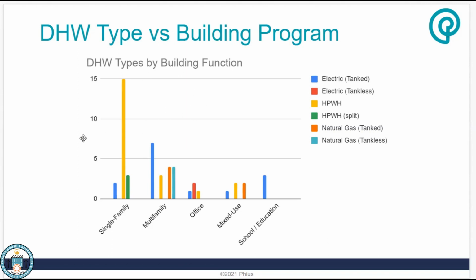So going back to this breakdown though, for single families, the vast majority are using heat pump water heaters, only a handful are using electric tanked water heaters. Multifamily is kind of the opposite: a lot of them are using electric tanks or natural gas systems. Typically the natural gas systems are big centralized units, like a Lochinvar centralized water heater or something like that, for the multifamily buildings, just because a lot of project teams are using engineers that have been doing natural gas water heaters for the past 40 years of their careers.